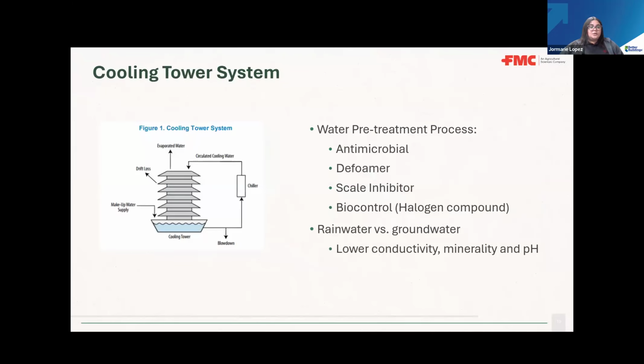Next slide, please. So for our site, the cooling tower is a crucial unit. This cools down the water from multiple equipment, such as condensers from the refrigeration machines, air compressors from our nitrogen generation machines, condensers from solvent recovery units, and other process equipment across our manufacturing process. So warm water from the process equipment enters the cooling tower header, falls through some nozzles that allow it to break down into droplets and then are further split by splash bars. As the water falls, air is driven by fans that are controlled by VFDs to keep the temperature around 78 degrees, causing evaporation to remove heat and water vapor.